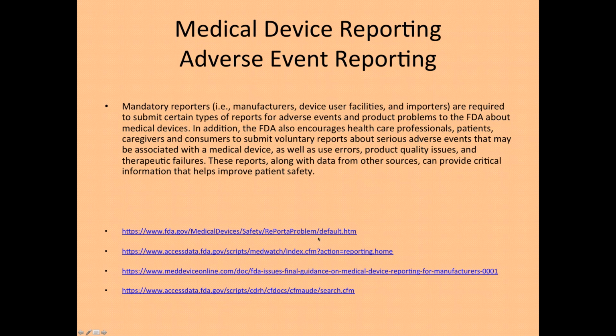And so there's 4 good links at the bottom. The one at the very bottom is the MAUDE search. MAUDE is the FDA's website that you can go on and see what people are being cited for, what kind of deviations have merited them some kind of a warning letter or a 483, and also what kind of problems they've incurred.